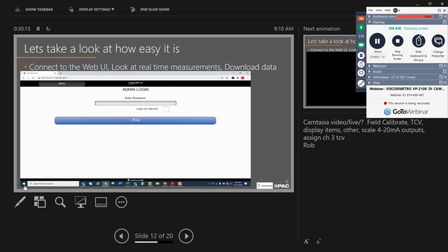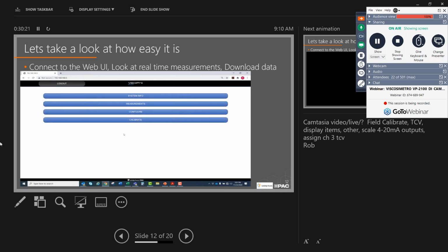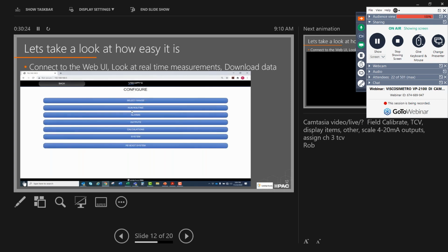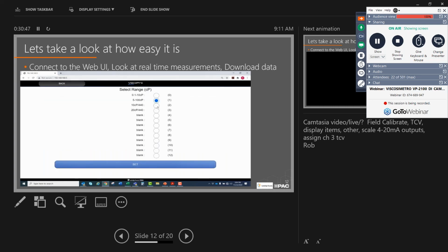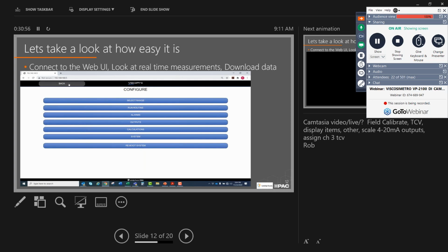You can then log in there as administrator, and you can make changes to the configuration of the system. So as you see, there's an additional screen there, configuration. So let's say, as an example, my ViscoPro 2100 had 3 different piston ranges in there. So I have a 1 to 20 and a 100 to 2000 range. So I wanted to change the piston. I wanted to do a different measurement range. So going through here, this allows you to set the different piston ranges. So this is one of the configuration settings.